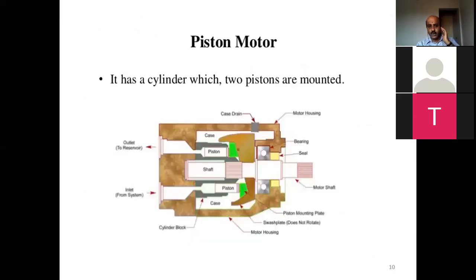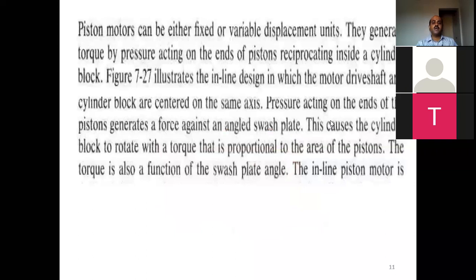The third type is the piston motor. Piston motors can be either fixed or variable displacement units. They generate torque by pressure acting on the ends of the pistons. In the inline design, the motor drive shaft and the cylinder block are centered on the same axis. Pressure acting on the ends of the pistons generates a force against the angled swashplate.